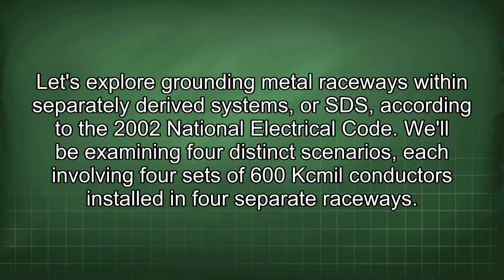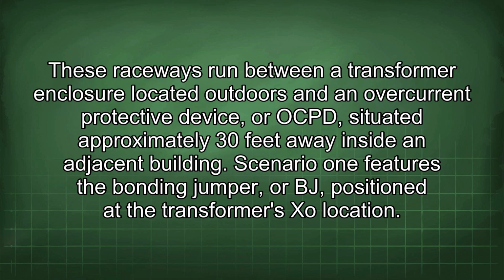Let's explore grounding metal raceways within separately derived systems, or SDS, according to the 2002 National Electrical Code. We'll be examining 4 distinct scenarios, each involving 4 sets of 600 kcmil conductors installed in 4 separate raceways. These raceways run between a transformer enclosure located outdoors and an overcurrent protective device, or OCPD, situated approximately 30 feet away inside an adjacent building.